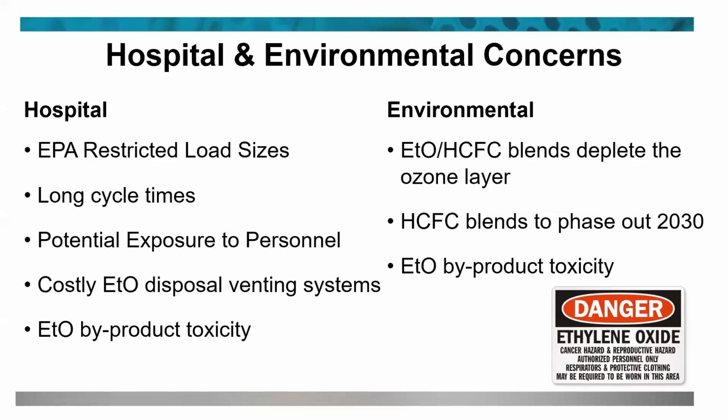So some concerns that we have with the hospital and the environment. The EPA has restricted the load sizes on here. You're supposed to only process full loads in your sterilizers. And the rule does allow for less than a full load to be processed in emergency situations.